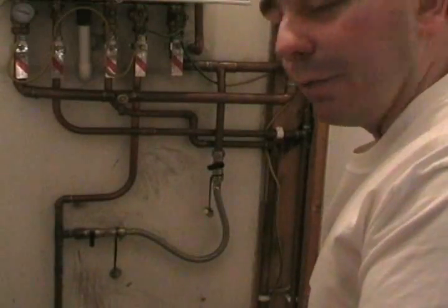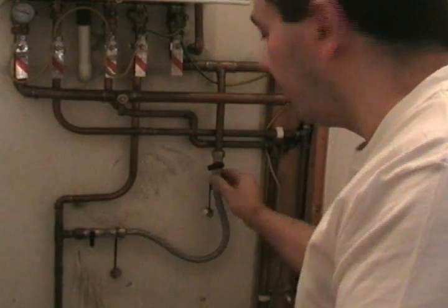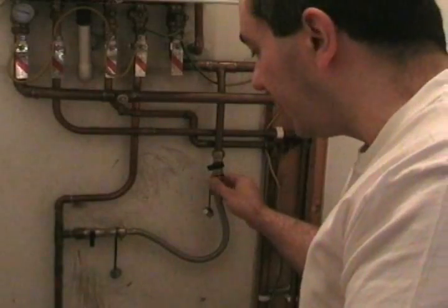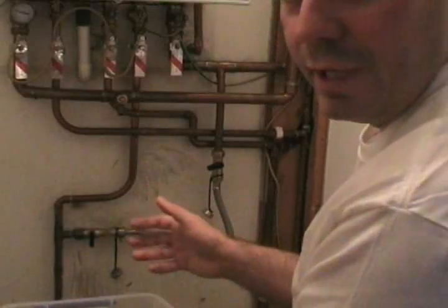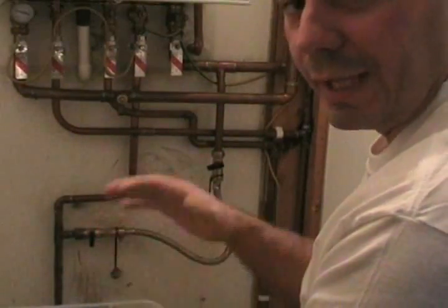Right, we've got one bar of pressure in there now. Now by law, you're not supposed to keep the filling loop connected to the boiler — you're supposed to disconnect it. When you've got the boiler at one bar, you might find that when you bleed the radiators, you're going to let more air out of the system, so you'll have to put a bit more water in to keep the pressure up.